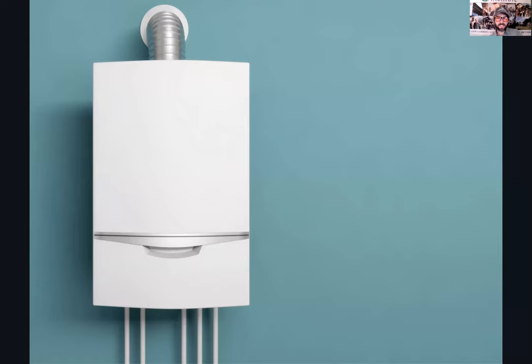And these devices, they don't run out of hot water. So that's great. And they are much more efficient. They're always sealed combustion, so that's good. They're healthier. But there are problems. One of the problems is maintenance. It's costlier. It's got to be flushed more often. It can clog up more often.